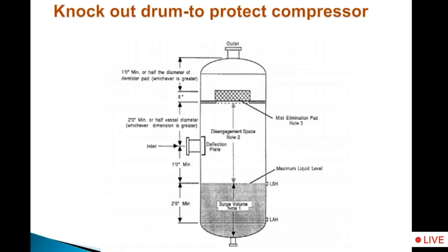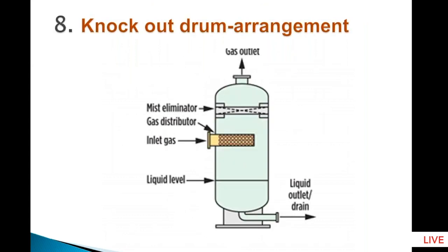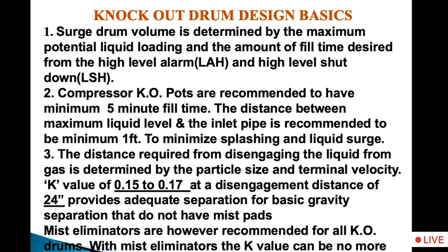So the liquid which is coming out along with the gas does not enter the compressor. It goes first into the knockout drum. Only then the gas is sucked by the compressor and the liquid is kept inside the knockout drum. There is a demister pad also to eliminate liquid going to the compressor, and this is an important vessel in case of accidents. I don't use a knockout drum in any of my plants because my accumulator or my LP vessel is properly designed. But I am giving you a suggestion. Use this vessel, plant operators or designers who are facing the problem of liquid coming to the compressor. This is a knockout drum, and this is knockout design basics.